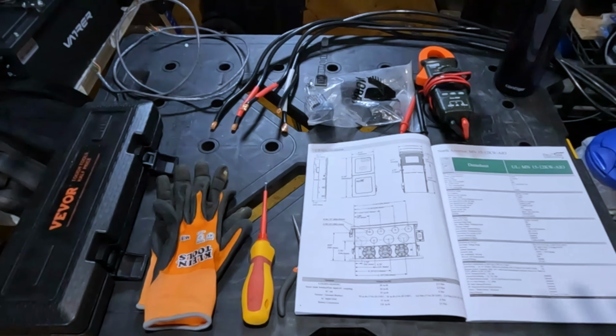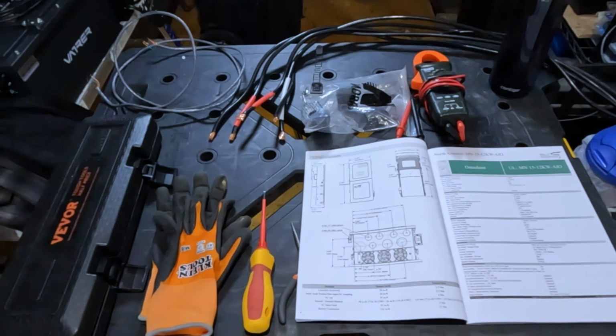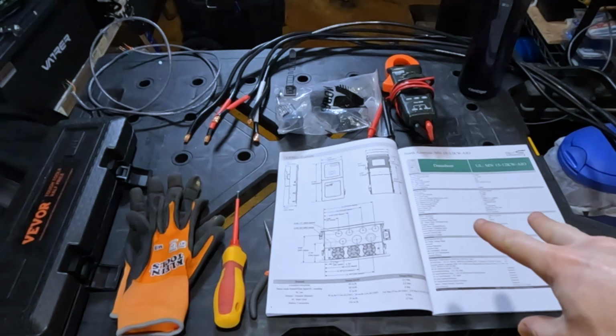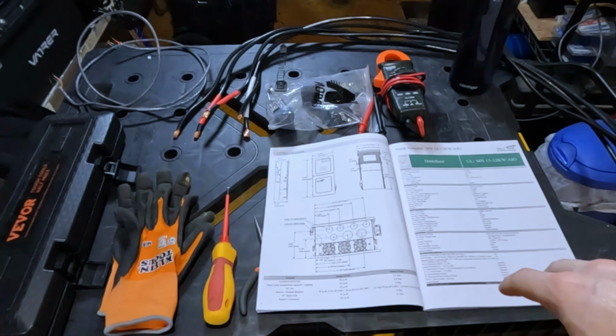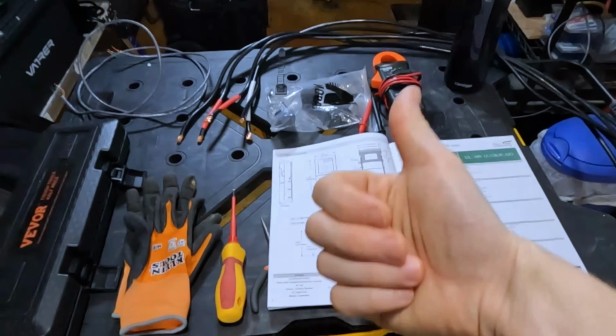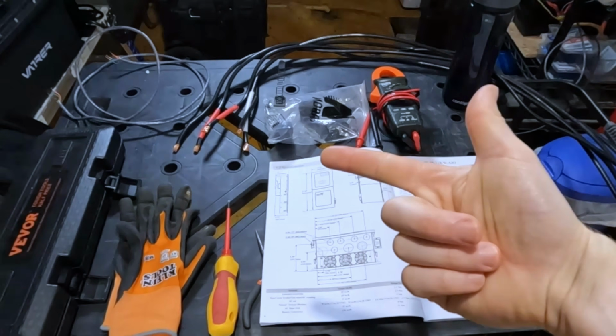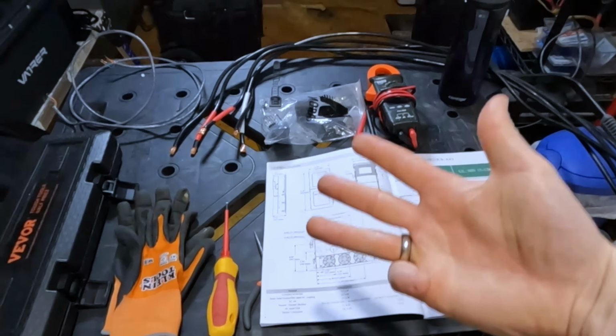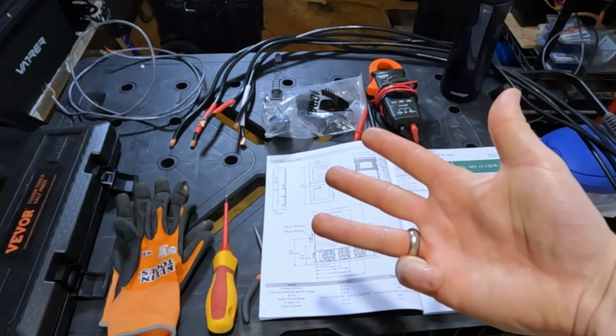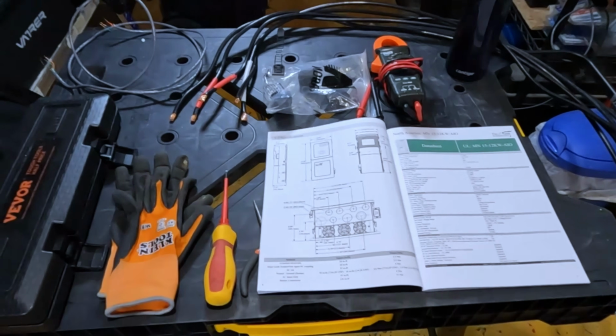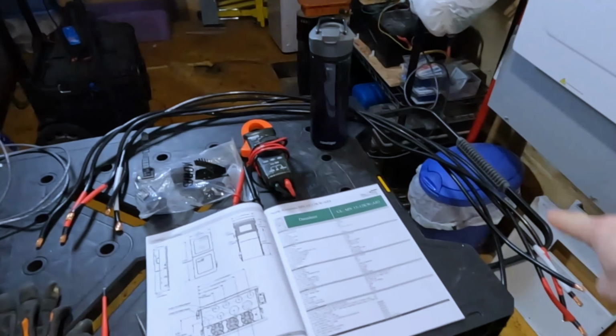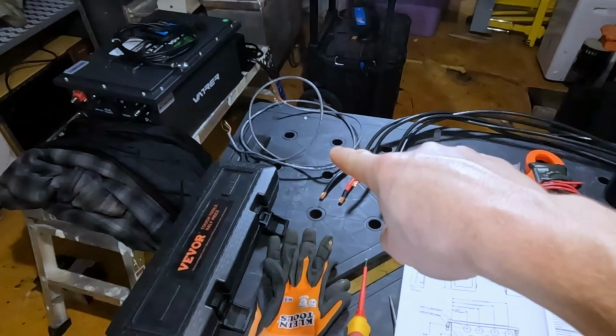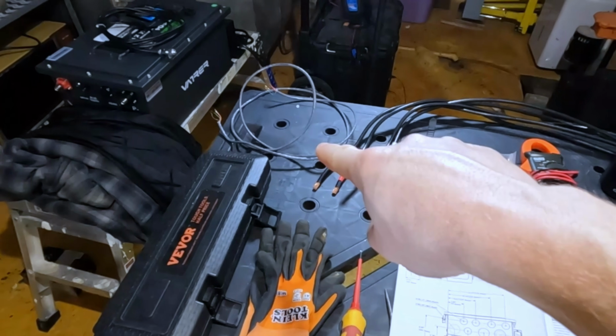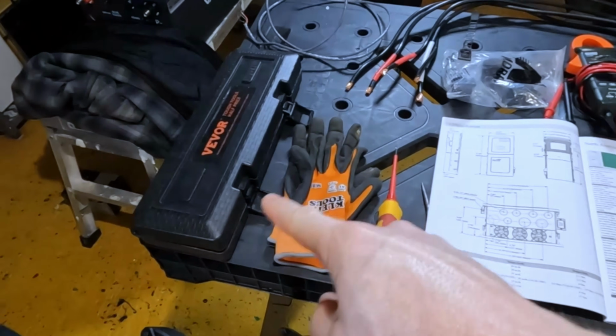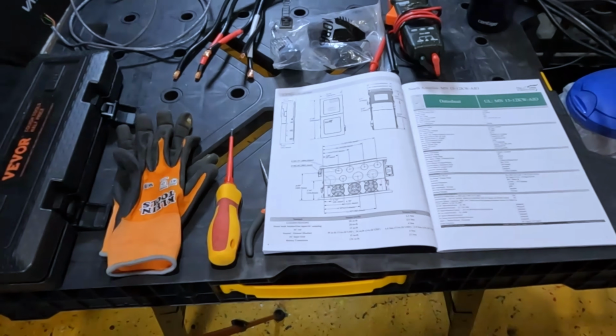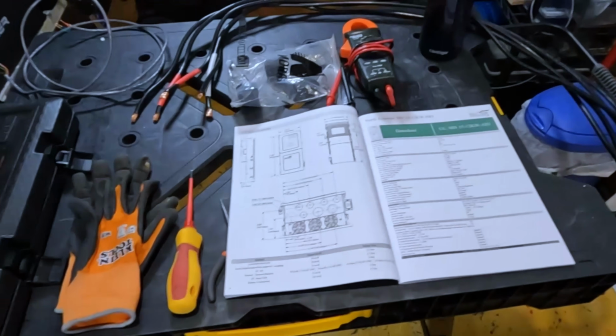So I've got on the table a lot of the different components that we're going to need in order to parallel these two inverters. The manual does a very good job of explaining what needs to be done, and there's really not a lot. You've got your AC connections, you've got your battery connections, you've got a paralleling cable, and then you program the parallel connection. I mean, that's really about it. So I've got our cables already cut to length for the AC connections. We've got a cat cable over here for our parallel cable. We'll use a torque screwdriver, some gloves, a pair of pliers, a flat blade screwdriver.